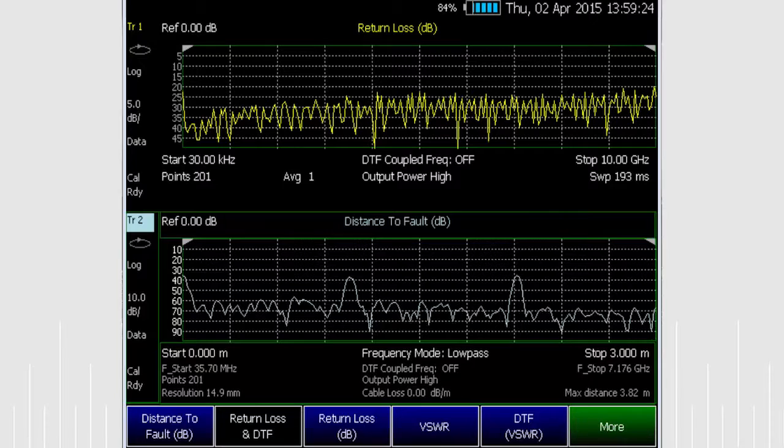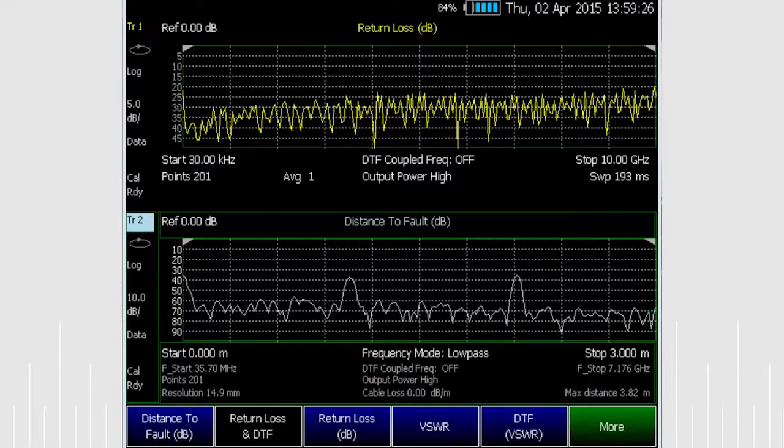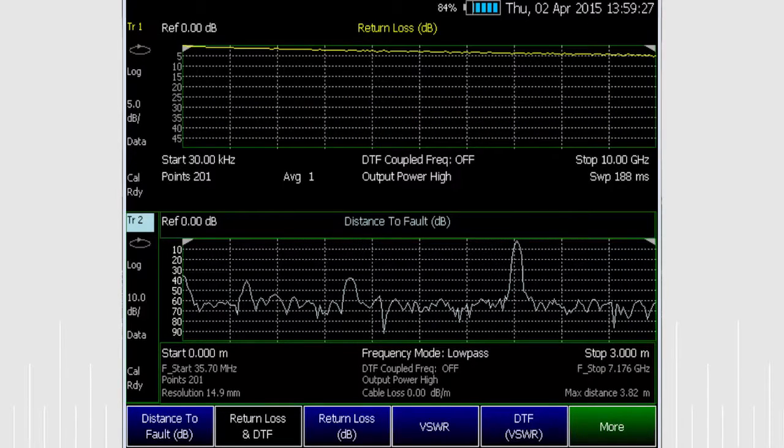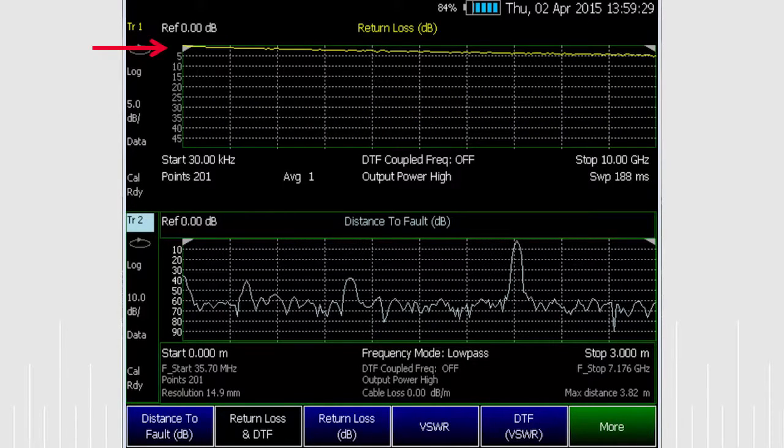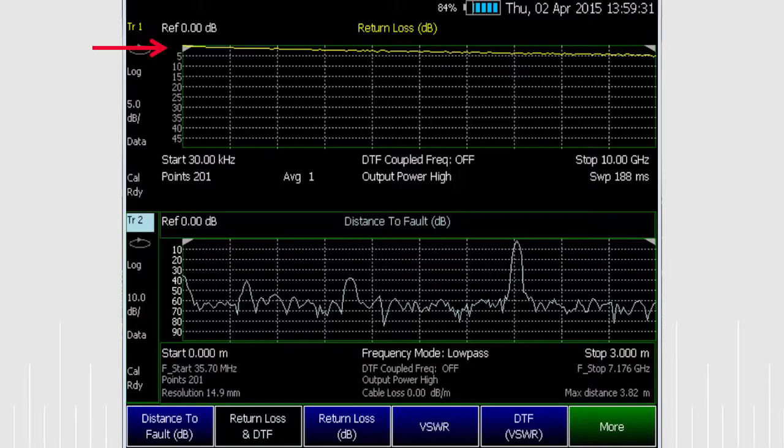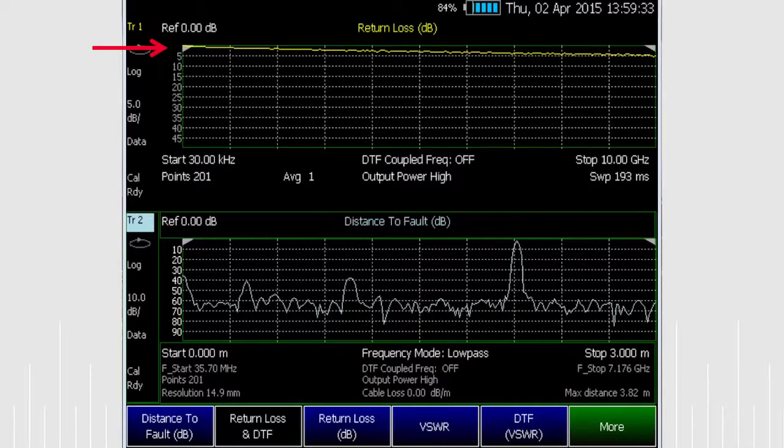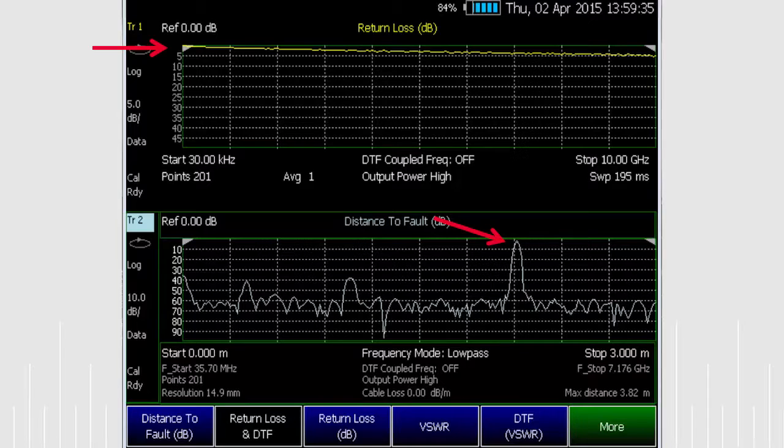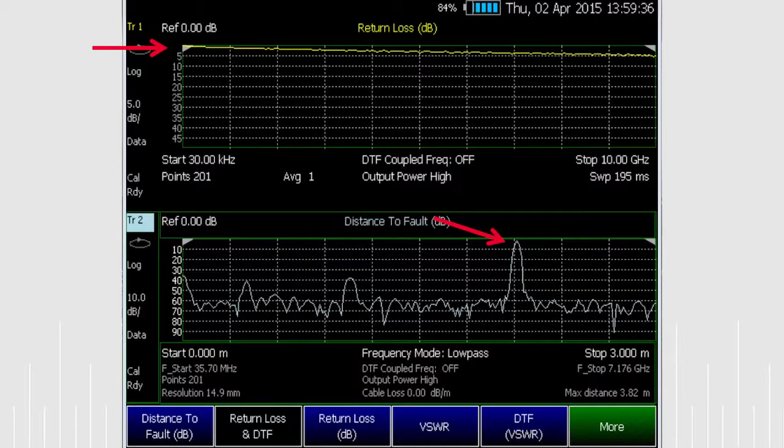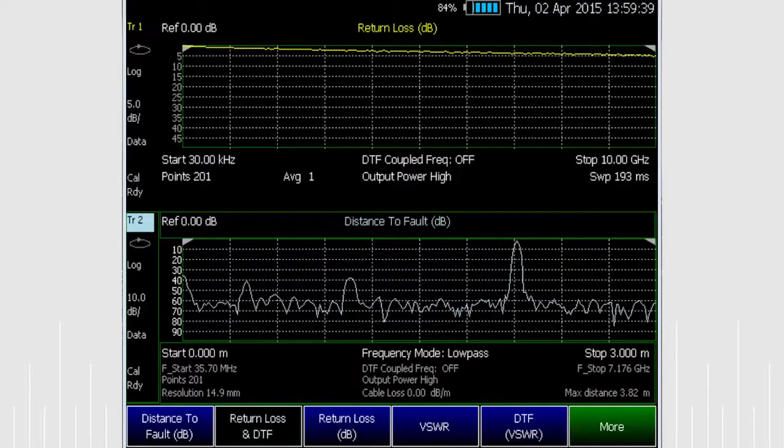Now I'll introduce a fault by loosening this adapter. You can see that we have almost all of the incident power reflected back in the return loss screen and that we have a large reflection down the line, but we don't know the nature of the fault. Let's tighten the adapters.